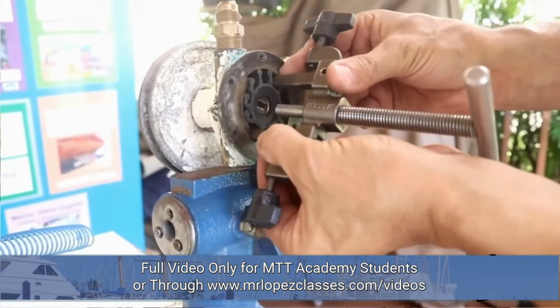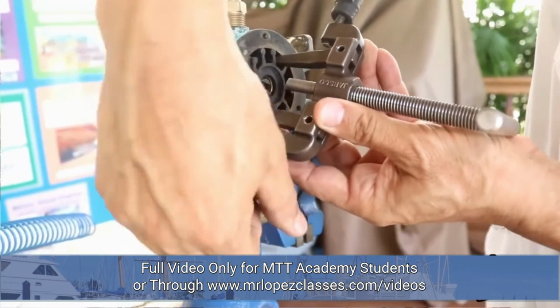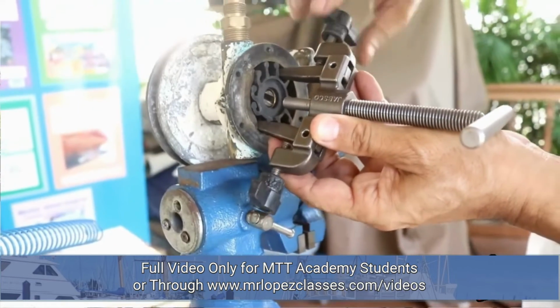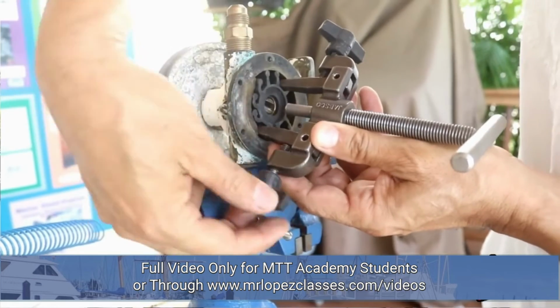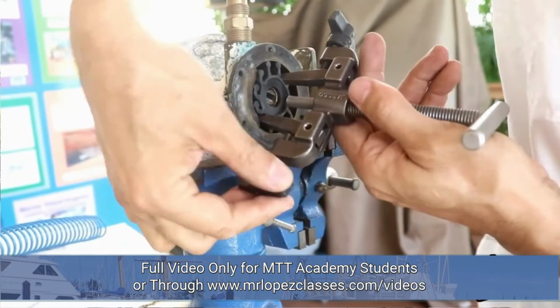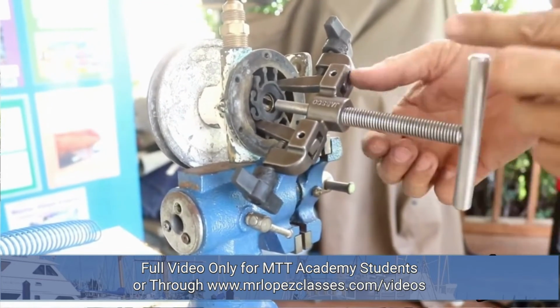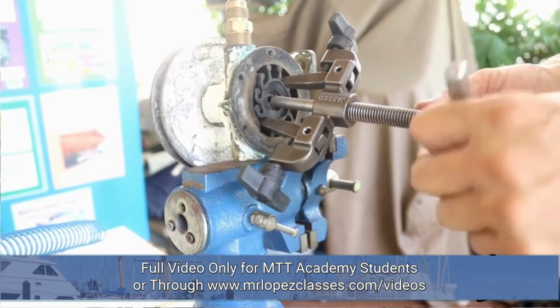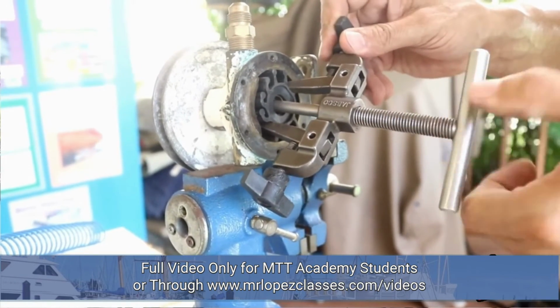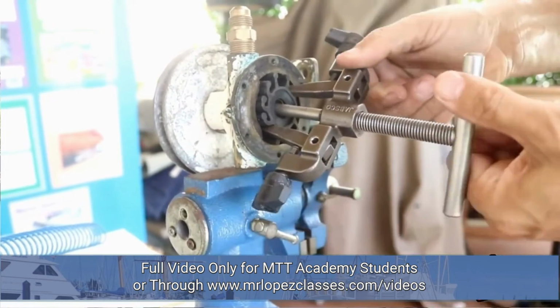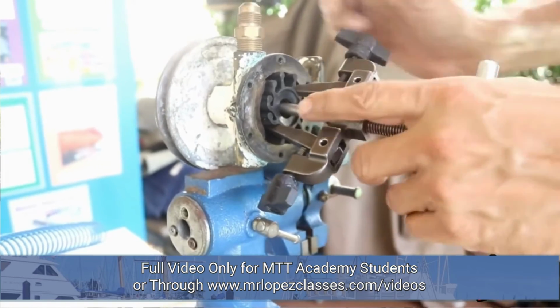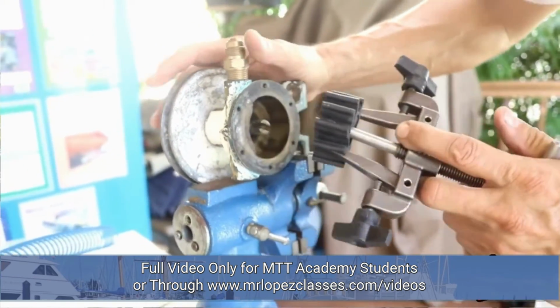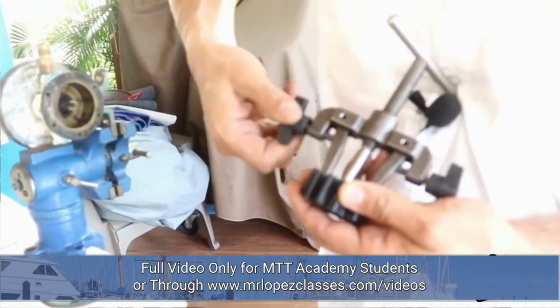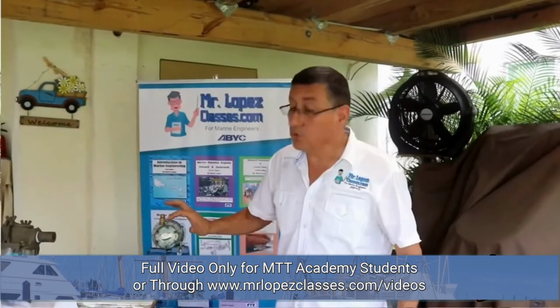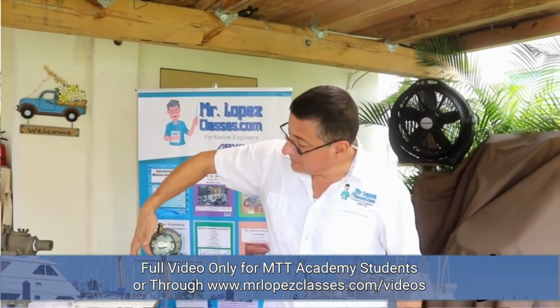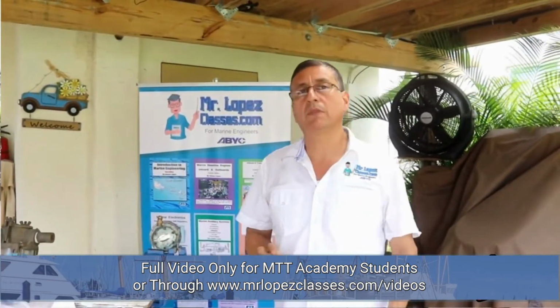This is the tool. We are going to try to use the tool right now. We are going to close both ends. We are going to close both ends properly. And now we are going to apply pressure in the middle in order to remove carefully the impeller. And right now we have the impeller. The impeller is ready to be replaced. As soon as you start the engine, verify that you don't have leaks in the bottom of the pump, and that the pump is running properly.